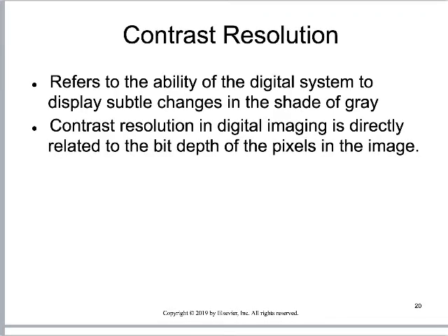Contrast resolution refers to the ability of an entire digital system to display subtle changes in shades of gray. Contrast resolution in a digital image is directly related to the bit depth of the pixels in the image. Contrast resolution for a digital imaging system is related to bit depth — how many different shades of gray can any given pixel within the image receptor represent.